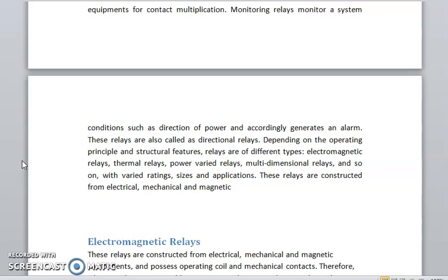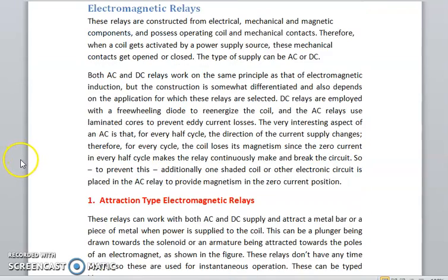Depending on the operating principle and structural features, relays are of different types: electromagnetic relays, thermal relays, power varied relays, multidimensional relays, and so on. With varied ratings, sizes, and applications, these relays are constructed from electrical, mechanical, and magnetic components. Electromagnetic relays possess an operating coil and mechanical contacts. Therefore, when a coil gets activated by a power supply source, these mechanical contacts get opened and closed. The type of supply can be AC or DC.